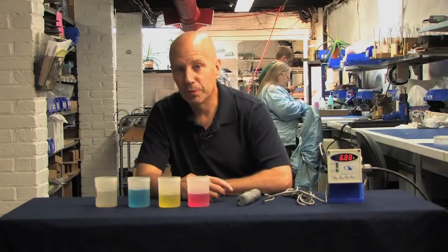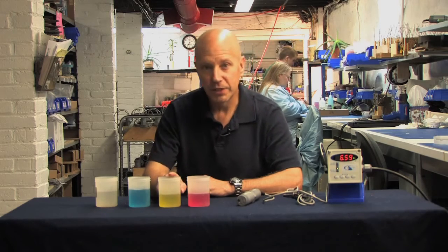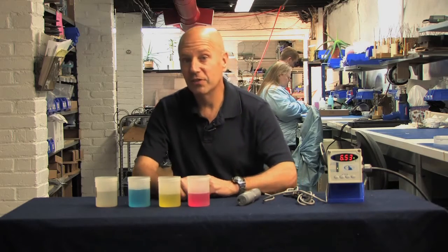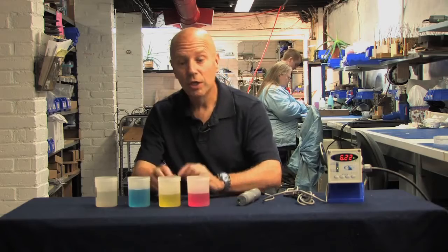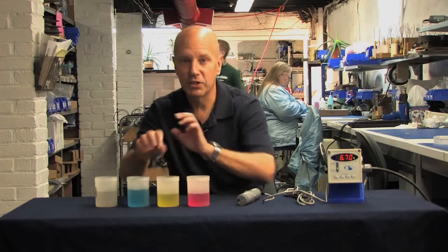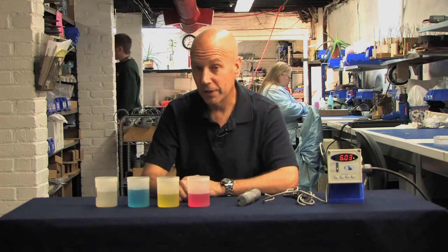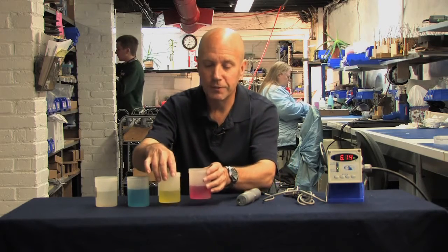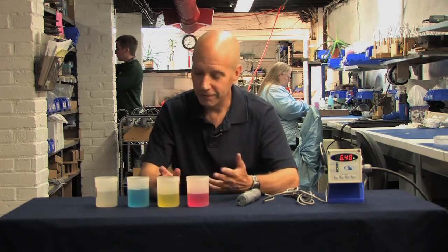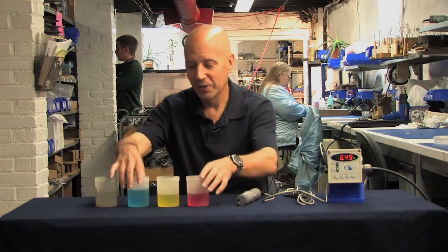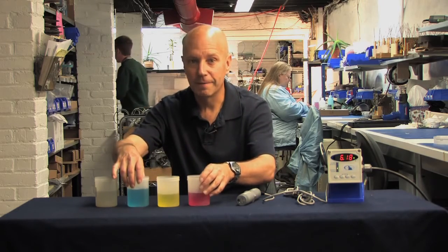To calibrate a pH probe, we need two of three possible pH calibration solutions: pH 4, pH 7, and pH 10. Now, if your process is on the caustic side, that is to say a pH greater than 7, you want to use pH 7 and pH 10. If, on the other hand, it's on the acid side, that is less than pH 7, you want to use pH 4 and pH 7. And if your process is all over, you'll need pH 4 and pH 10.